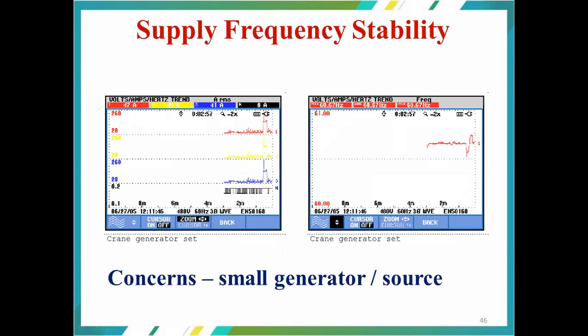So the supply frequency stability is again going to be a concern when it comes to a small generator or source, because we are going to have the synchronization process on and off. Thereby, we are going to have the stability issue in terms of the frequency. For the given case, the frequency is mentioned as 60 plus or minus 1. The frequency is continuously monitored in all the phases, which ensures that it is completely within the given range.